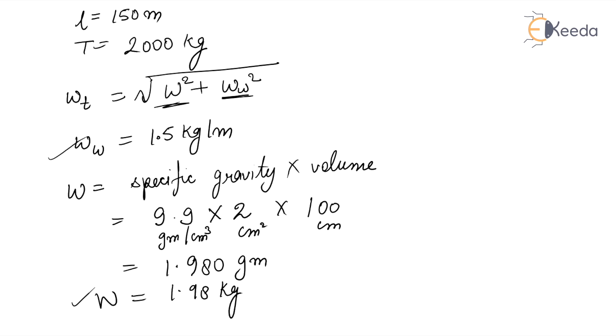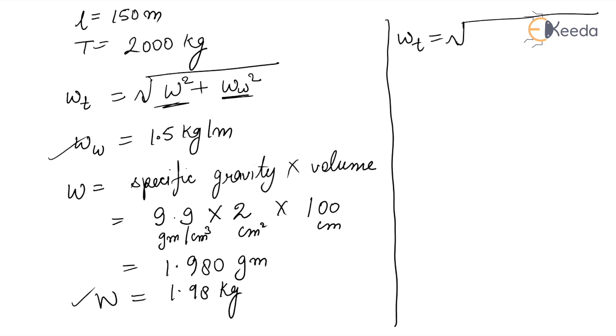Now put the values of W and WW into the WT formula. WT = √(W² + WW²) = √(1.98² + 1.5²) = 2.48 kg. So the total effective weight of the conductor per meter is 2.48 kg. Now we put this effective weight into the SAG formula.